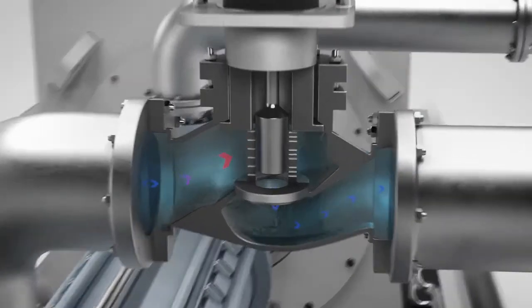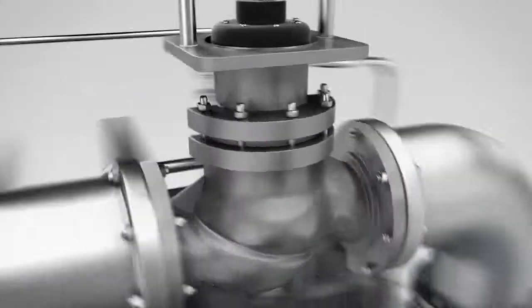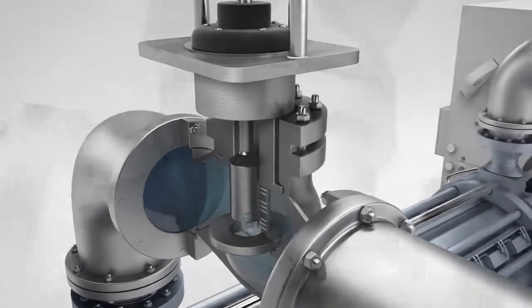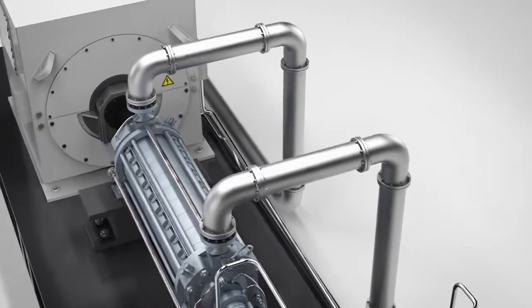At the same time, the throttle valve experiences wear through cavitation, resulting in the expensive proposition of replacing valves, along with a high level of vibration-induced noise. Energy waste, high maintenance costs, and inadequate reliability make discharge throttling a poor choice for modern power plants.